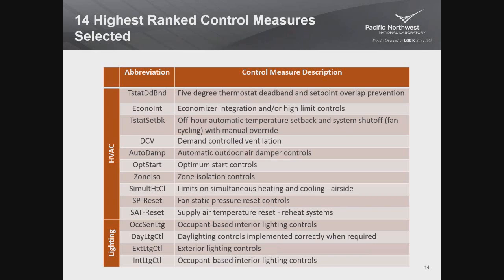And then there's some high limit control requirements that says you can't shut off the economizer until it reaches certain high limits, which are different in different climate zones. Sometimes it's dry bulb temperature. Other times it's humidity levels. Thermostat setback. That's the one that we talked about previously with the automatic temperature setback, 55, 85, and the manual override and the 7 schedules.